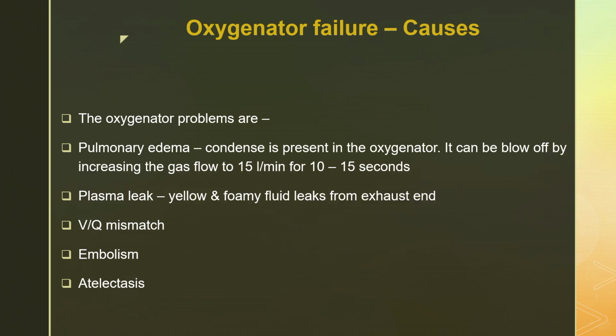So what you need to do is every 4 hours increase your sweep gas to more than 10 liters. Because of the increased sweep gas pressure, the water molecules that accumulated and condensed there will come out. You will literally see, from the exhaust of the gas line, water molecules dropping. That is what we call a sigh. Like the way you give a sigh ventilation, every 4 hours you have to do this for the membrane, just blowing out the condensated water. That is what membrane edema is.